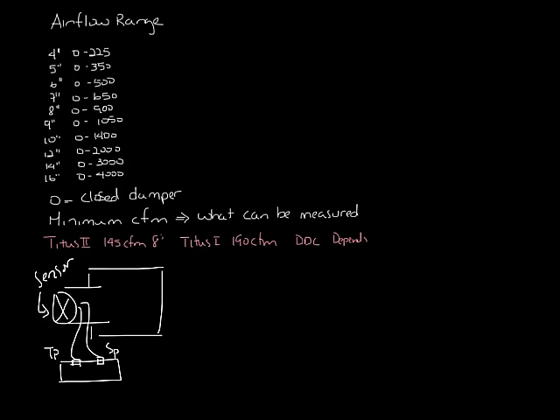If you recall, the difference between total pressure and static pressure is the velocity pressure. So the controller uses the velocity pressure to calculate the velocity of the air moving through the box. This is velocity equals 4005 times the square root of the velocity pressure, and then it can use that to calculate the CFM, which is velocity times area.